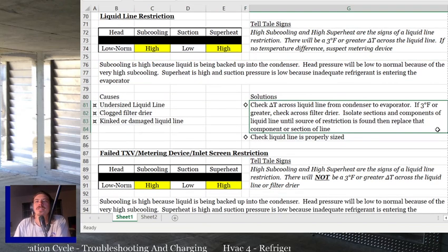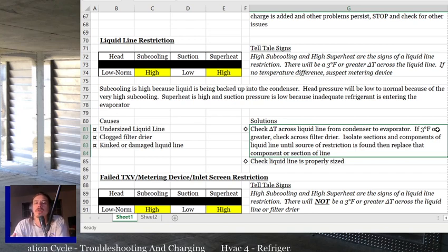Alright, causes for the liquid line restriction are undersized liquid line. So if you're supposed to have a 3/8 liquid line and you got a 1/4 inch, that's a restriction. Clogged filter dryer is kind of your most common, and then your kinked or your damaged liquid line is the next most common. So the solution is check for the delta T across the liquid line from condenser to evaporator. If you got a 3 degree or greater difference, check across the filter dryer. Isolate sections and components that you have in the liquid line until you figure out, okay, where's it at?